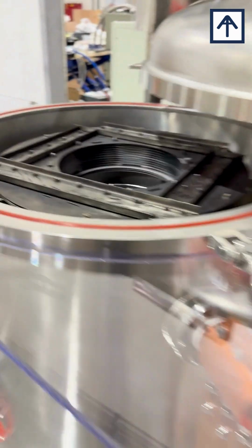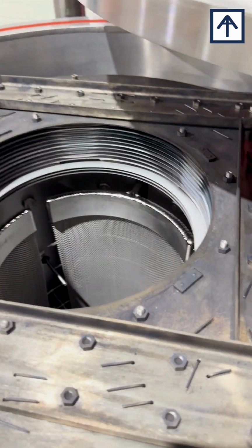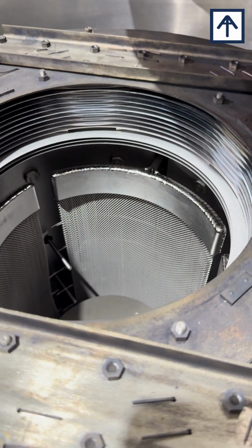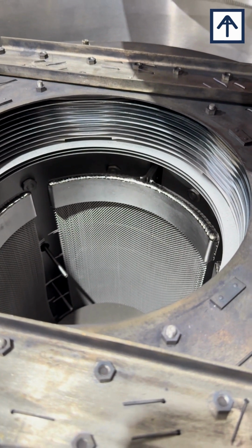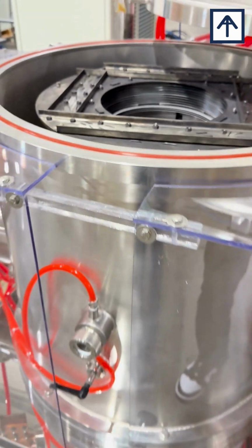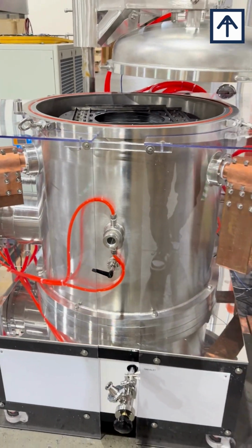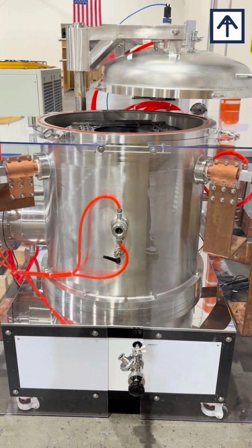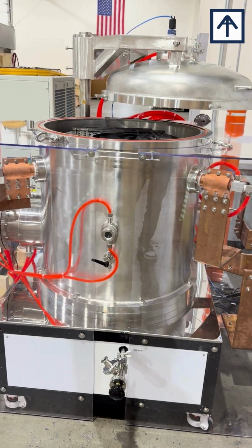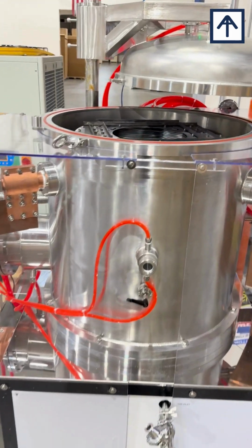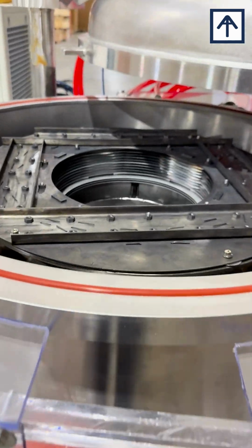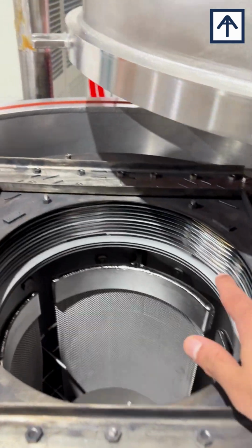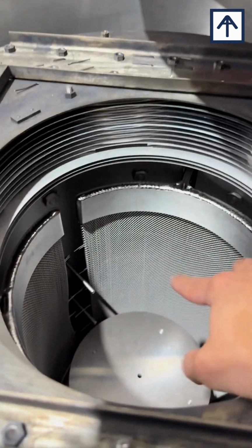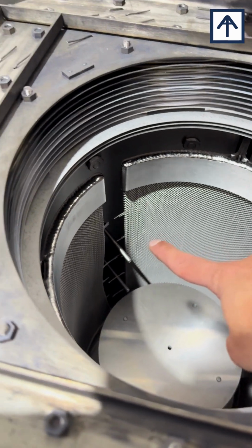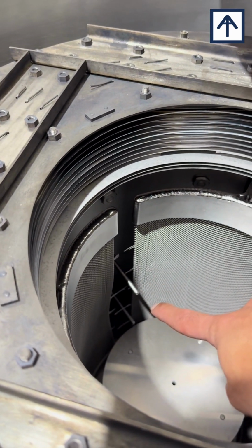The unit has tungsten heating elements in the chamber, ensuring long-lasting performance and built for extreme temperature resistance. The chamber on the unit offers a vacuum or inert gas environment to protect materials susceptible to oxidation. As you can see, the tungsten chamber and the tungsten heating element mesh, that's the bottom base plate, and those are the thermocouples, the primary and the secondary.